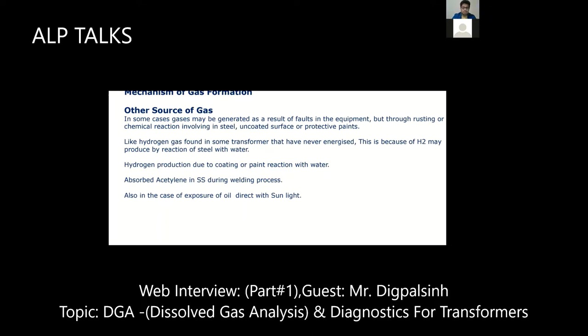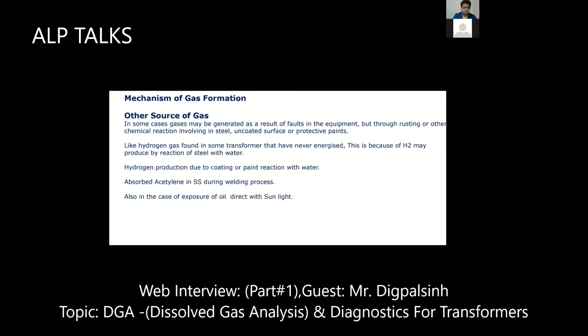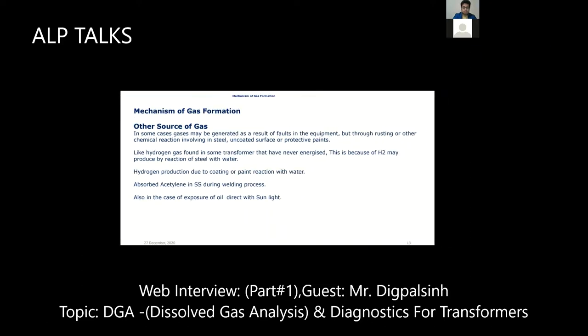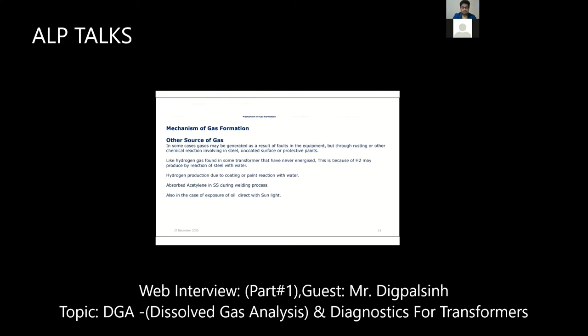Another case is if your oil is exposed directly to sunlight, at the time of filling the transformer tank, or on site, in case of a shutdown, when the transformer oil is taken outside and then refilled into the transformer tank. At that time, if the transformer oil is exposed to direct sunlight, not for 1 or 2 minutes but for a long duration, then hydrogen will also be produced inside the oil. So these are some other sources of gas formation inside transformer oil. Okay, that's it for gas formation.